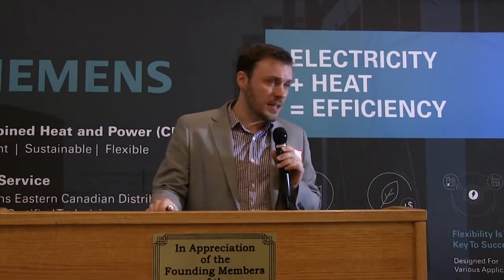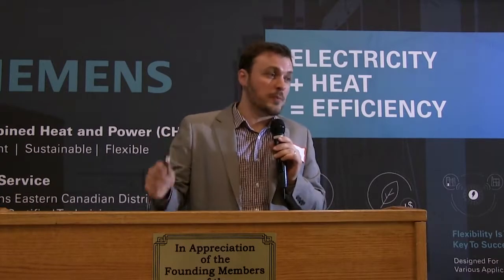On the co-generation side for CO2, you will already need an SCR to run a lean-burn unit — which is standard for continuous operation — but there is a price difference when you're talking about an SCR that will supplement your facility with CO2. You'd have to consider how much more you'll pay for that, plus whatever dispersion system you need — though that's covered in the alternative as well. Operational expenses are your annual SCR maintenance plus the urea that Lauren talked about.